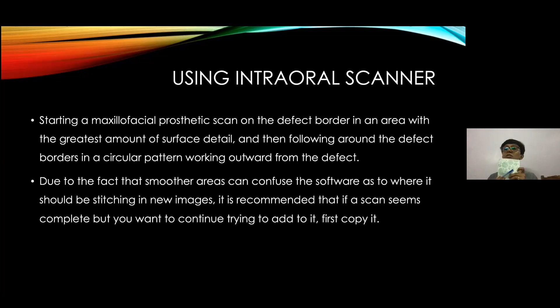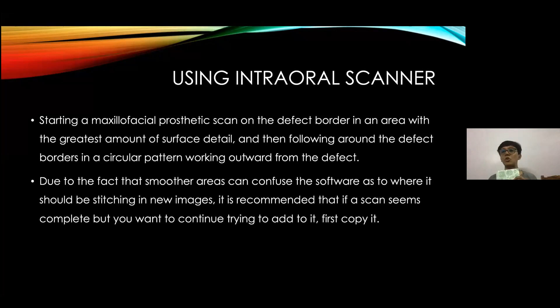But when we talk about a defect like a maxillectomy defect, the inside cannot be seen, the light does not enter there, and the scanner is not able to pick up a scan from there. That is one limitation of the intraoral scanner when we talk about scanning maxillectomy defects. Also, if the surface is smooth, then it is not able to stitch or align the previously recorded images. So that is one limitation of the scanner. These challenges are due to hardware and software limitations.